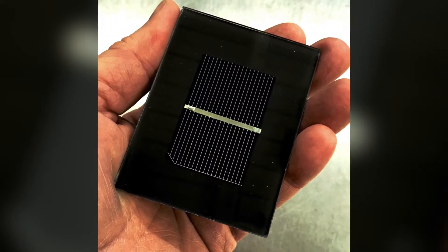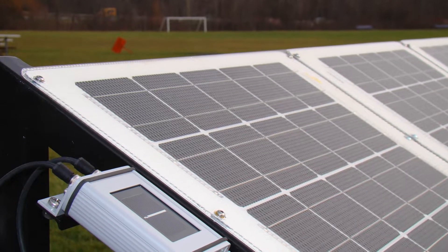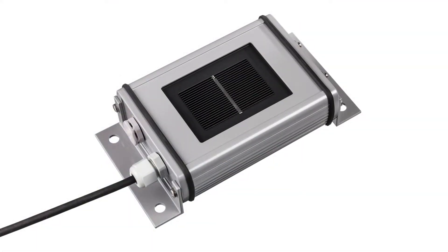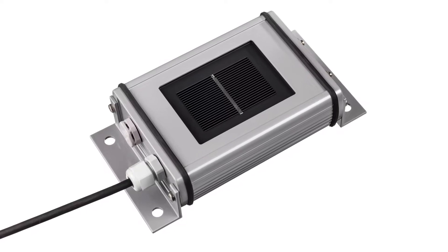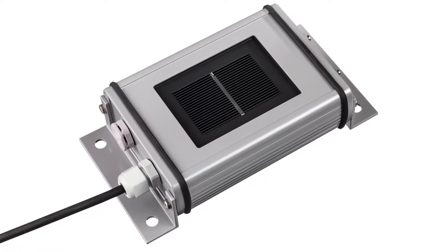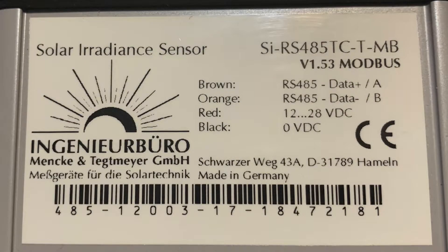With the proper technique, the initial solar cell platform is eligible to be used as an irradiance sensor, because the short-circuit current is proportional to the irradiance. By constructing the sensor from a monocrystalline PV cell section connected to a shunt, the low resistance of the shunt enables the PV cell to only operate very near a short-circuit condition. This now very stable but sensitive component is further enhanced to accuracy with temperature compensation.